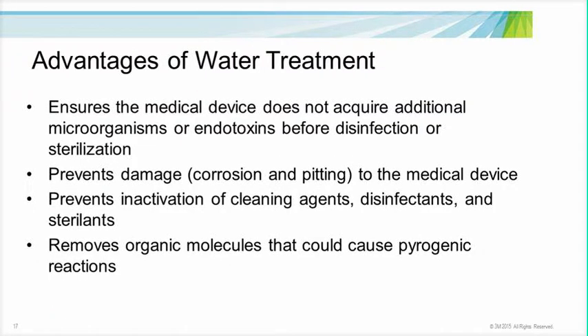To mitigate these risks, potable or drinking water is treated to reduce the amount of impurities and potential adverse effects they possess. This increase in the quality of water aids in the prevention of adding additional contamination from the cleaning process from microbial sources as well as oxidizing agents which may corrode or pit metal devices. Additionally, a high-quality water free of scaling minerals increases the efficiency and effectiveness of detergents.